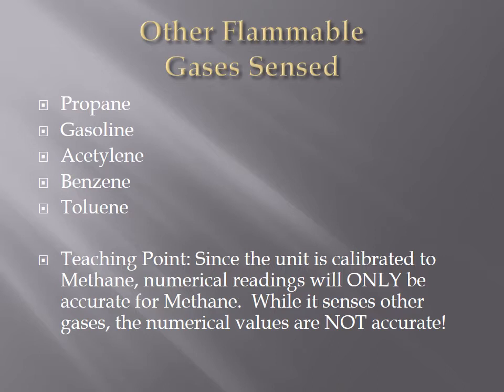But you don't know that. All you know is that you're going to have the audio portion of the monitor that is in alarm mode, but you're unsure if that is, for example, propane, acetylene, or maybe a benzene. So when you see the digital readout, that is only accurate for methane. Again, while it senses other gases, the numerical values are not accurate because it is calibrated to methane. So it's only really looking for methane and will display that on the screen.